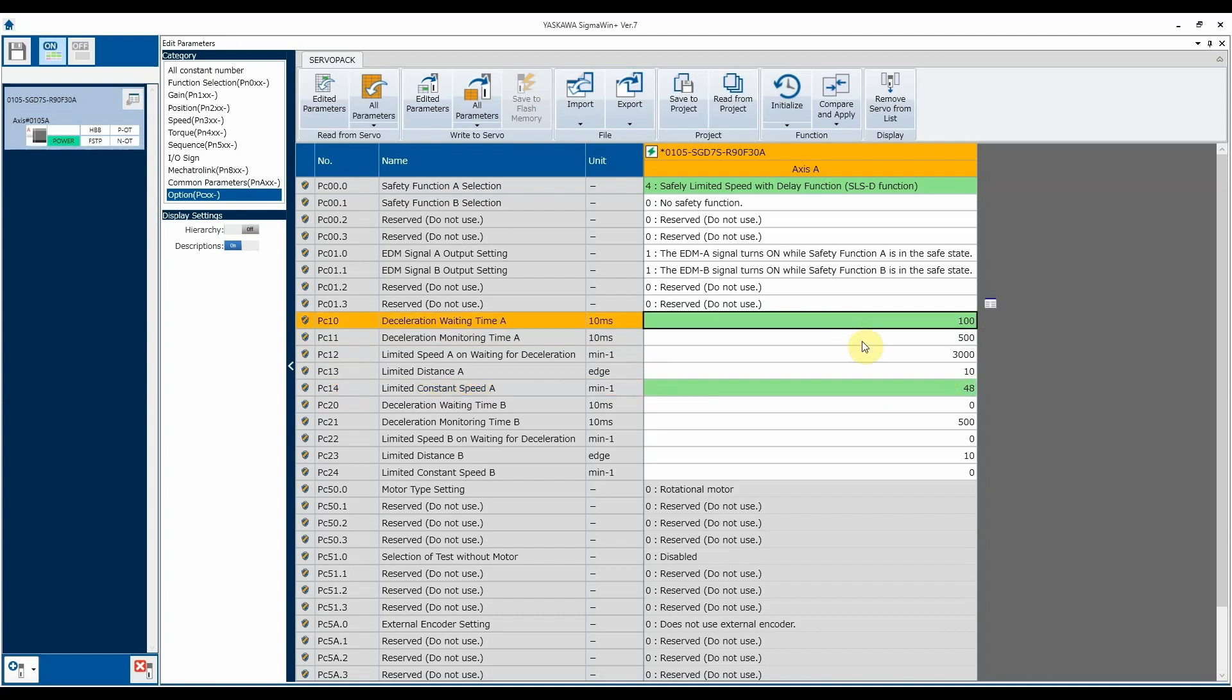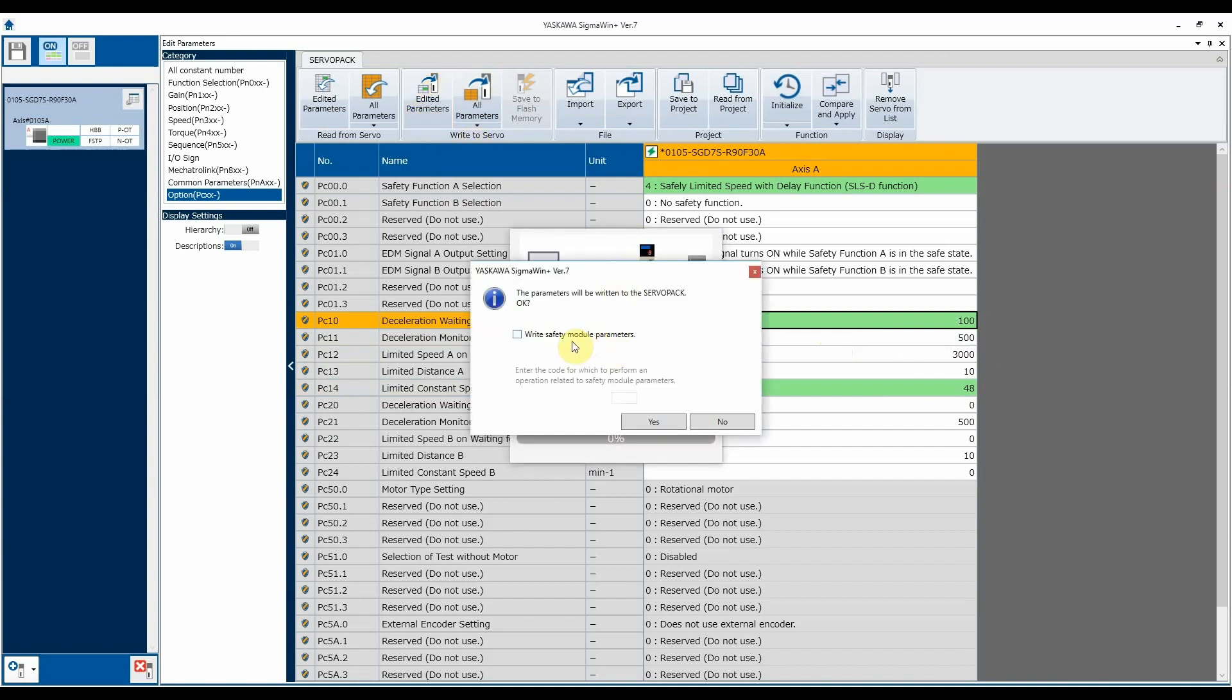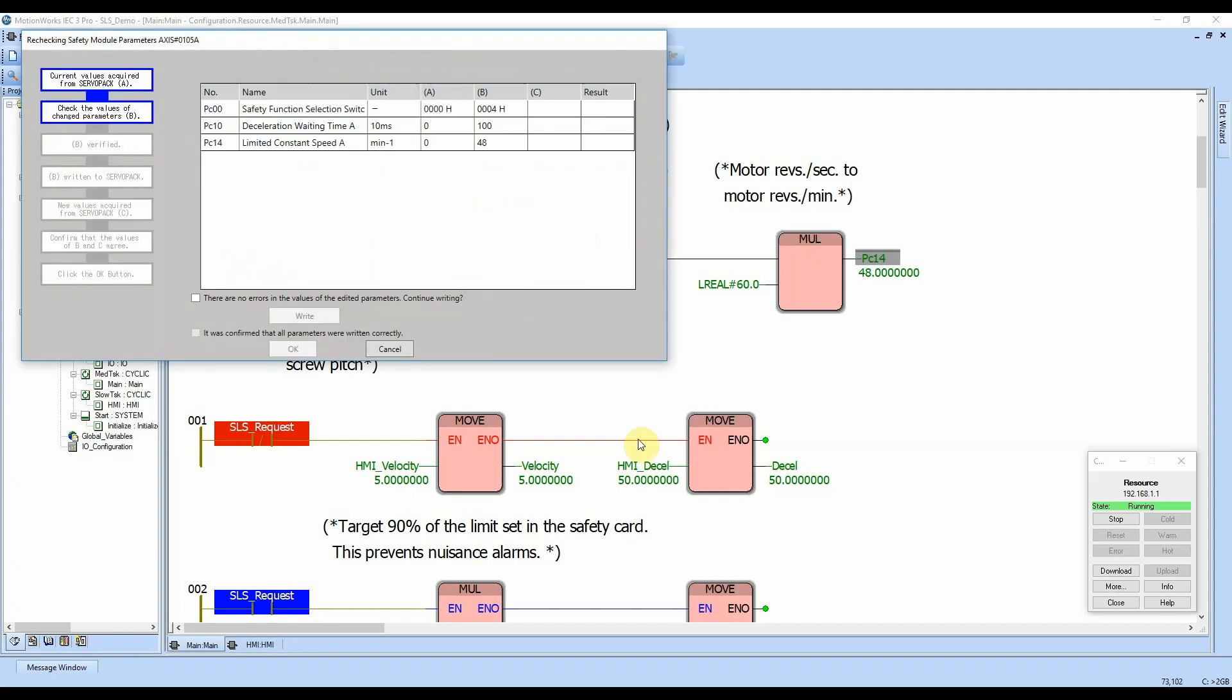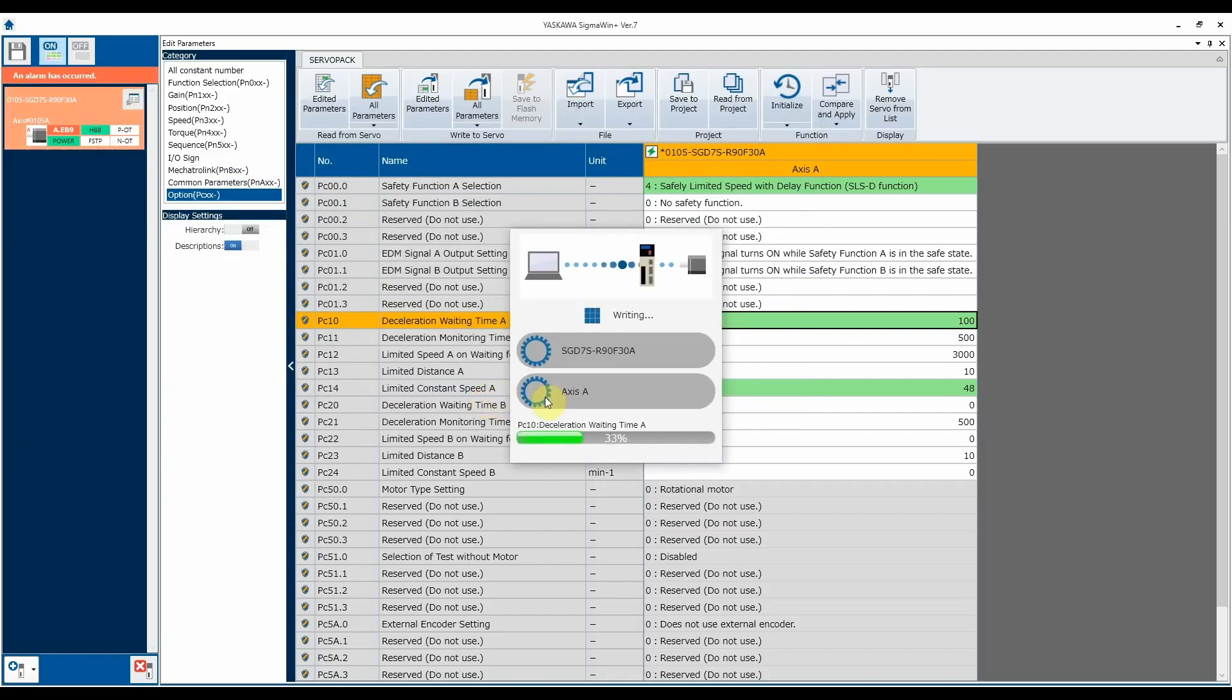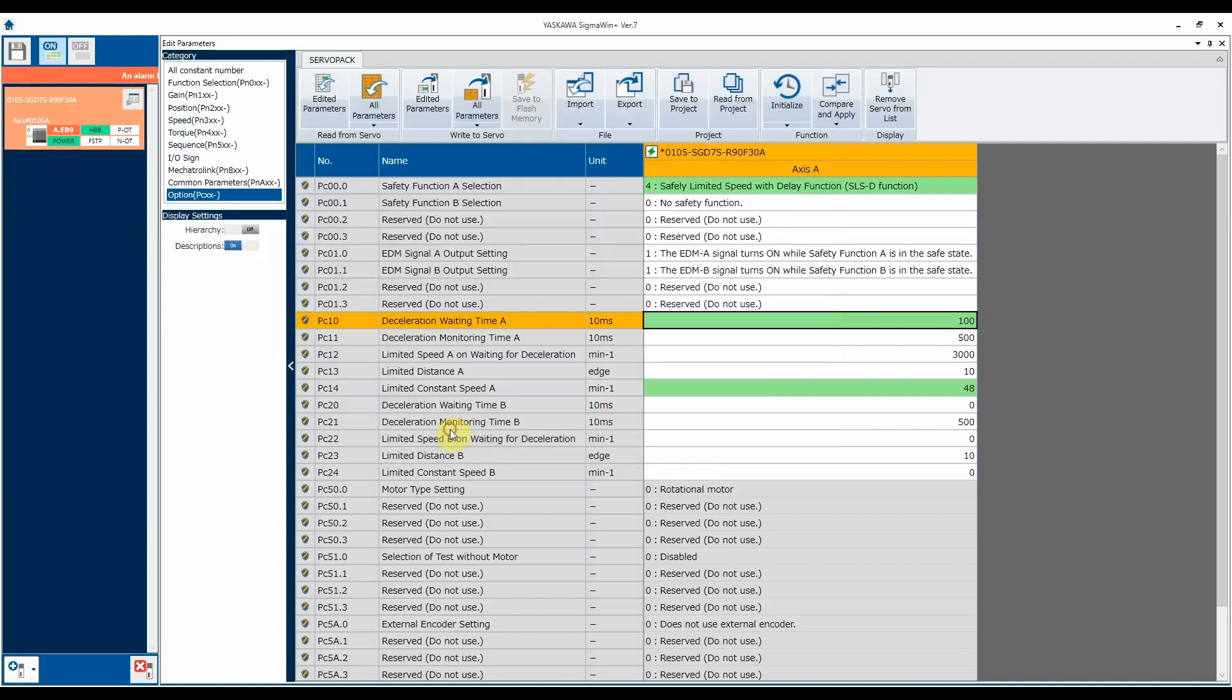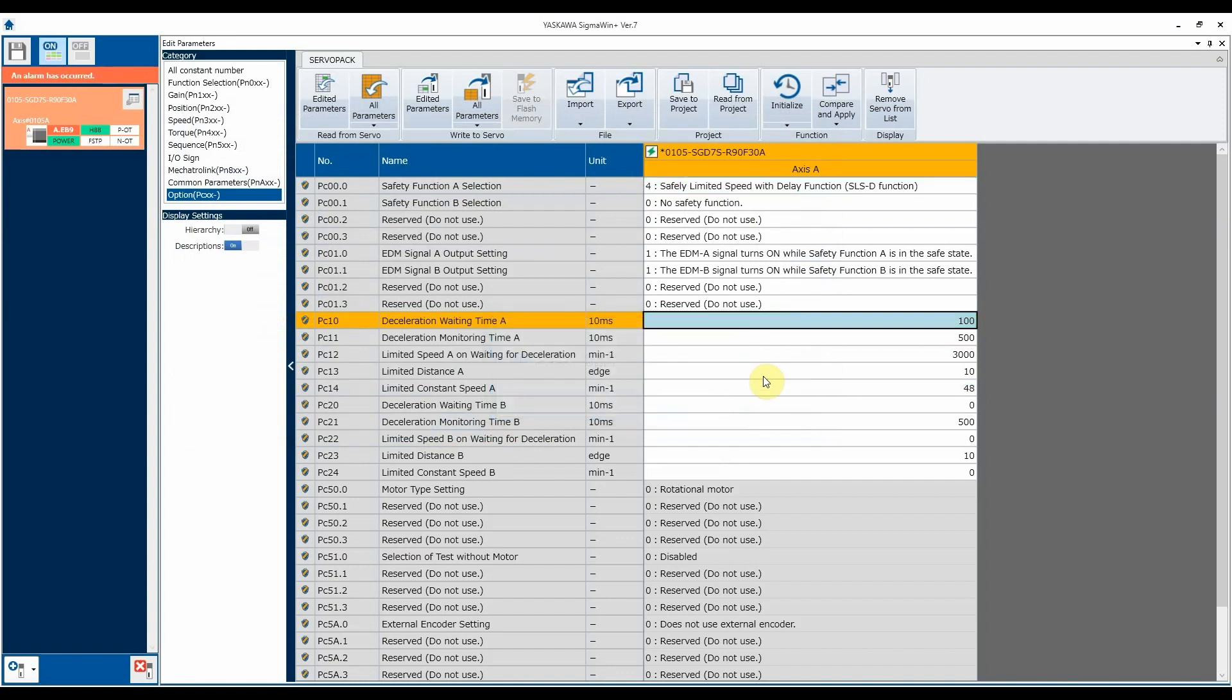These values being green aren't actually in the servo pack or safety option card right now. So we'll click on the edited parameters. It'll write those down. And it'll give us a little check saying do we want to write safety parameters. We do want to do that because it's going to ask for a code to implement those. The code's always four zeros. And then there's this little dialog box that might be new or you might have seen before. It only happens with safety parameters. So it's confirming that yes, that's really what you want to do. It's going to write those. There's going to be another one confirming that what it wrote is actually in there. And then the last thing is saying that these parameters won't take effect until the servo pack has been power cycled or it's been a software reset.